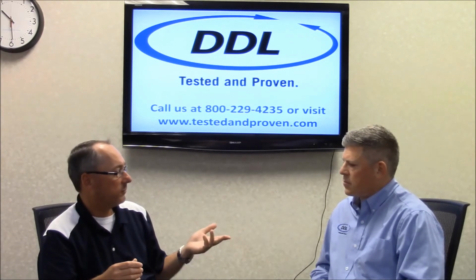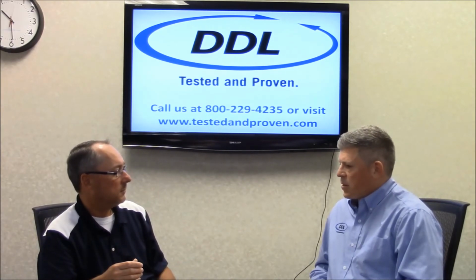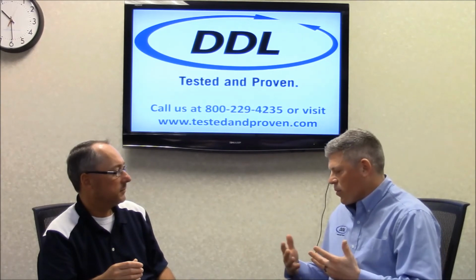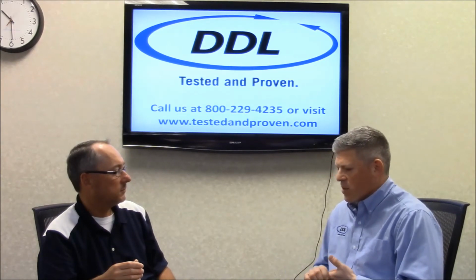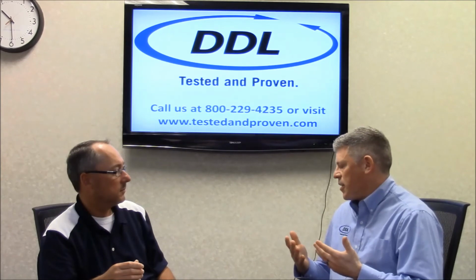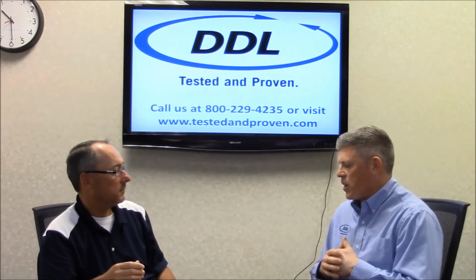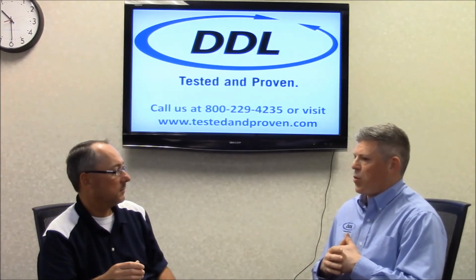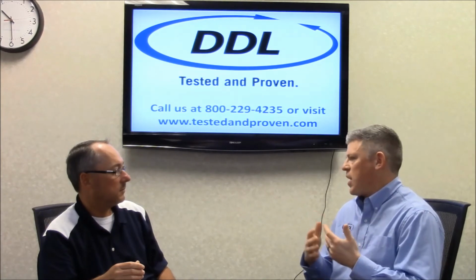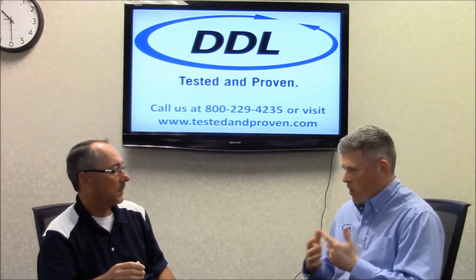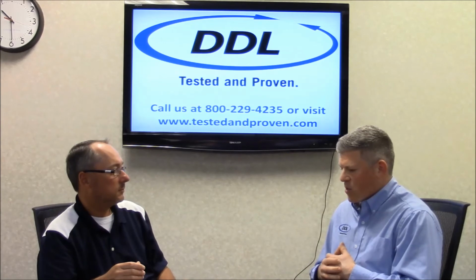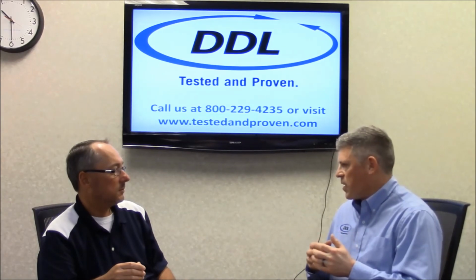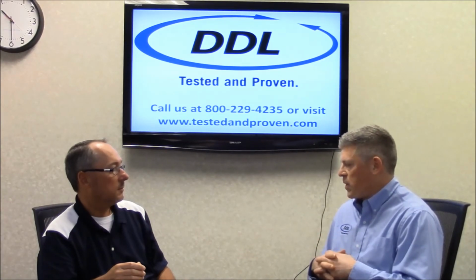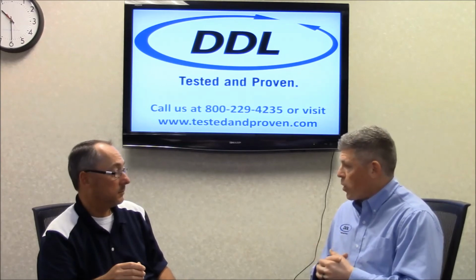How about yourself? Well, with the accelerated aging and my customers, like the standard suggests, not to go above 60 unless you are able to have written documentation on how those materials react. Yep. So I counsel all my customers on staying at 60 or below unless they have data support otherwise.